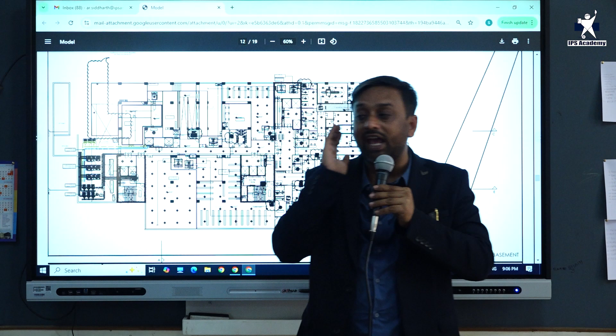Within 30 meters of staircase gap you should have a fire hydrant cabinet. Again, if you are having one electrical shaft at one end, you will lose length. So you should have it at the center so that the diversions are done and cable lengths are sorted.